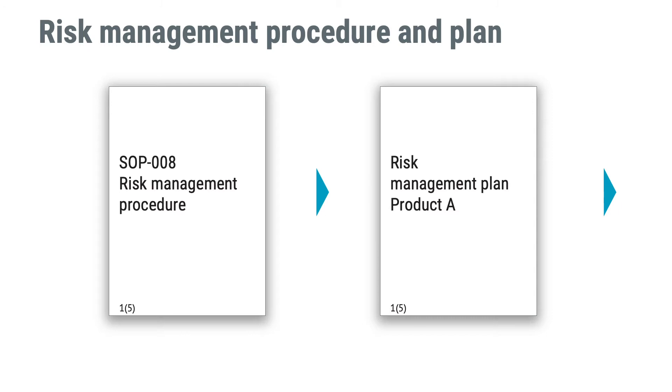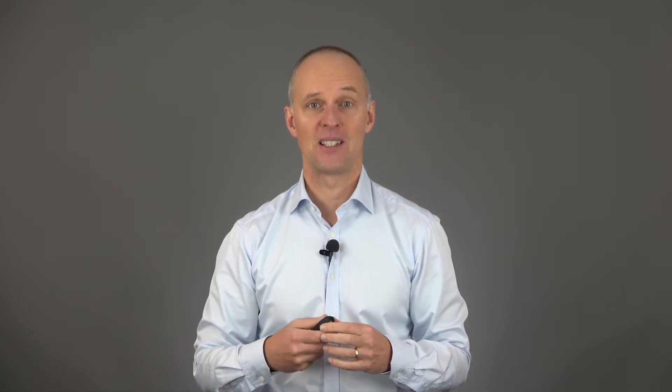Firstly, you should have a procedure in your company that tells you how to work with risk management. The procedure in turn should require you to make a plan for the risk management work to be done for a product or product group. The plan should outline who is responsible for what. Both notified bodies, the FDA, and ISO 14971 require people performing risk management to be competent, and having records proving that competence is also a requirement — for example, a course certificate.